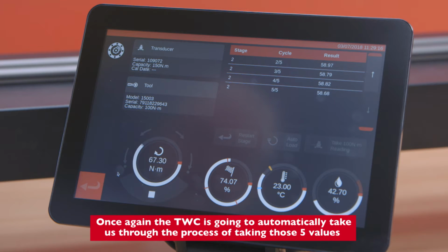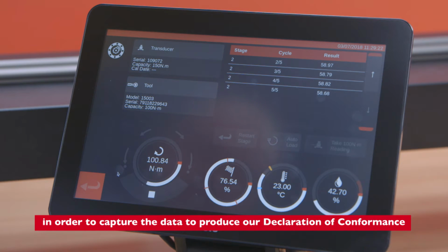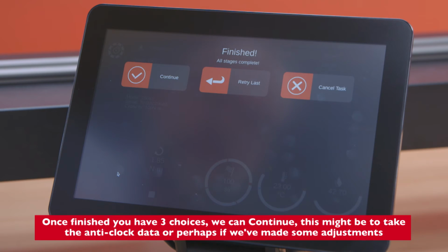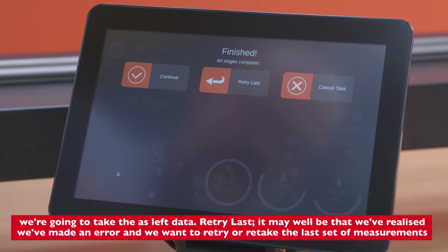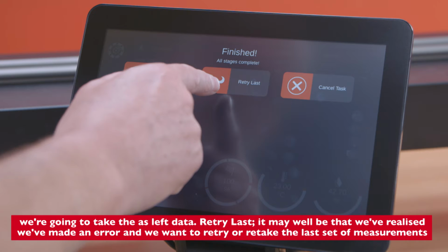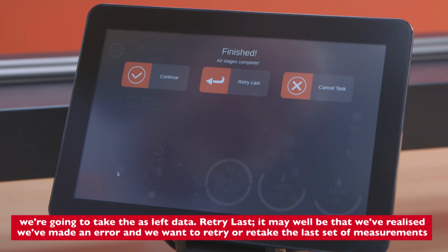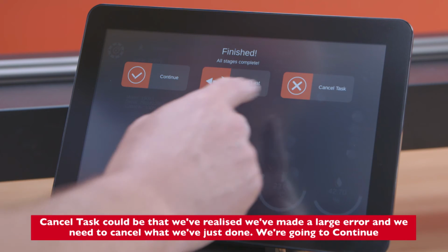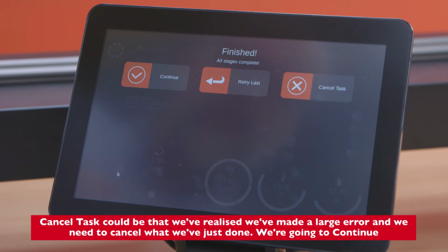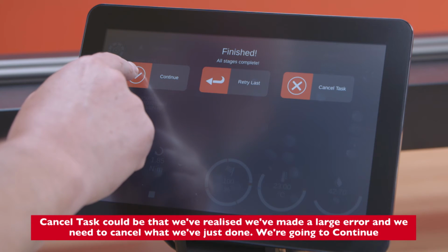Once again, the TWC is going to automatically take us through the process of taking those 5 values in order to capture the data to produce our declaration of conformance. Once finished, you've got 3 choices. We can continue. This might be to take the anticlockwise data, or perhaps if we've made some adjustments, we're going to take the as left data. Retry the last. It may well be that we've realised we've made an error and we want to retry or retake the last set of measurements. Cancel task could be that we've realised we've made a large error and we need to cancel what we've just done. We're going to continue.